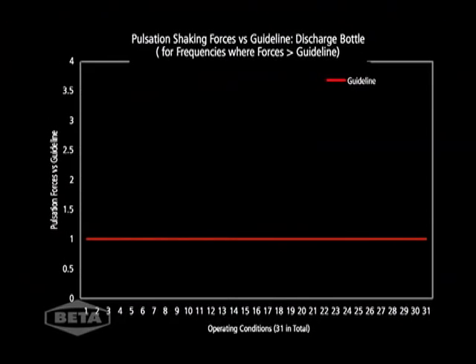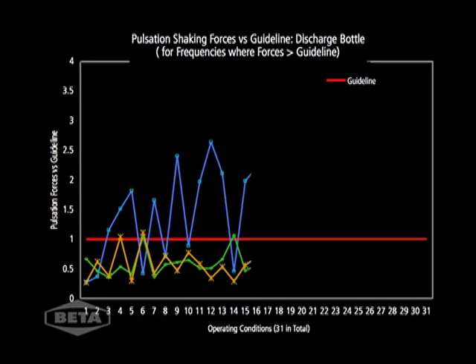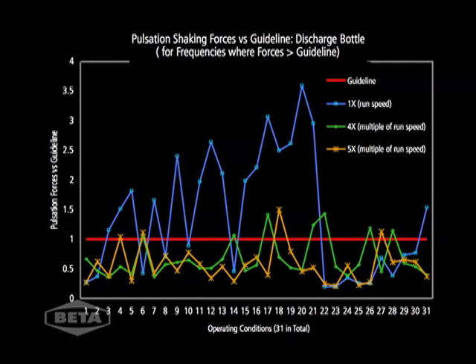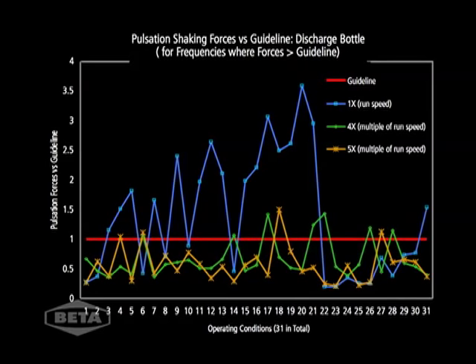Pulsation forces will be different at each condition. This chart illustrates the importance of analyzing all operating conditions. This compressor has 31 different conditions. At one times run speed, there are many conditions where the forces exceed guideline. We also have to catch problems at higher frequencies. In this case, we see some conditions where forces exceed guideline at 4x and 5x run speed.